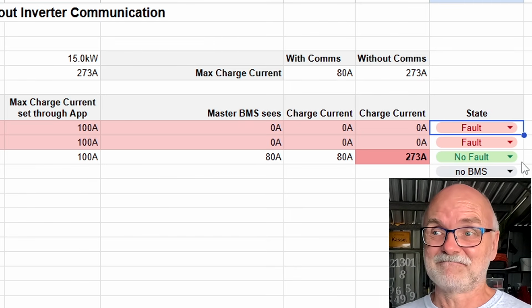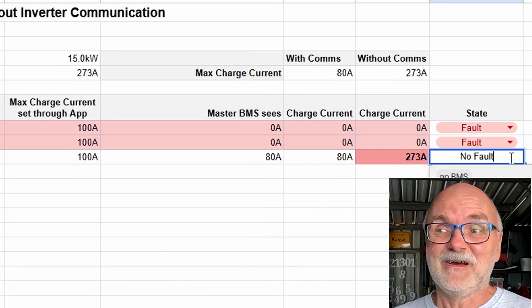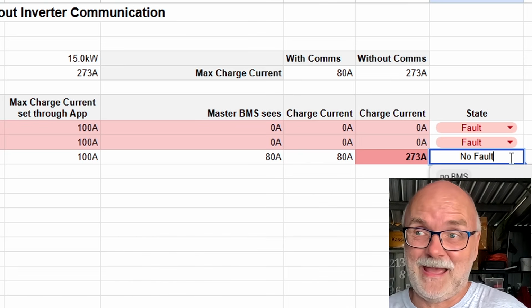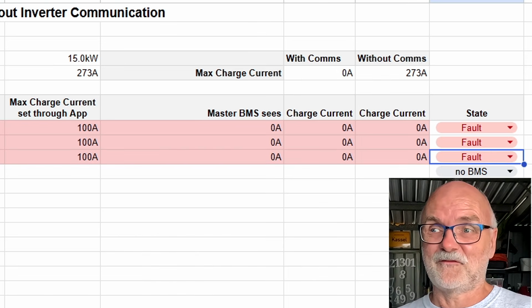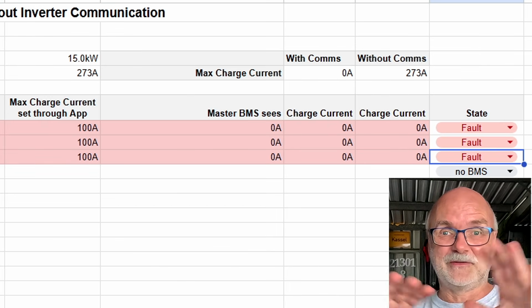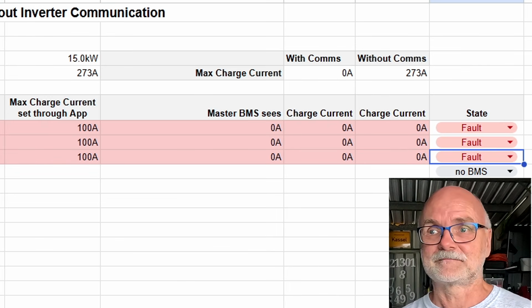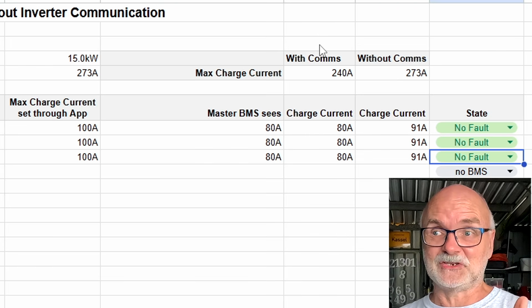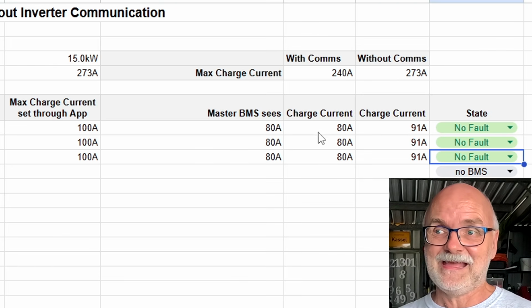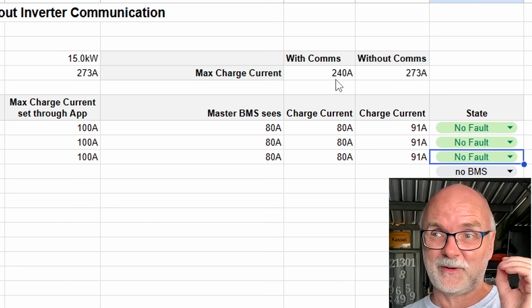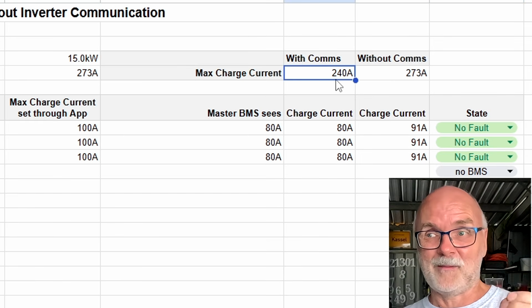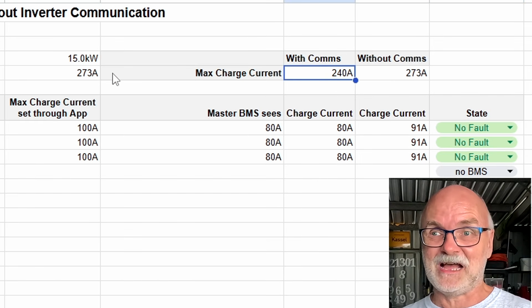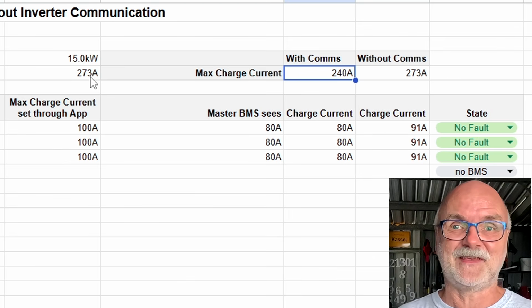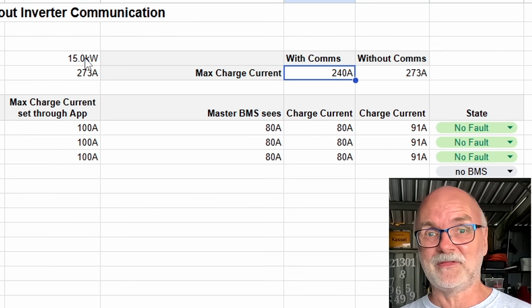So what happens? Exactly what happened to me. All three BMS, all three batteries are turning off. We've got a fault in all three and the whole system shut down. So let's do this quickly again with the communication. Looking at this column D here, 80 amps going into the battery. We are already throttled. We are requesting only 240 from the inverter, from the charger, but it can deliver 273. And this is a very common thing people do.